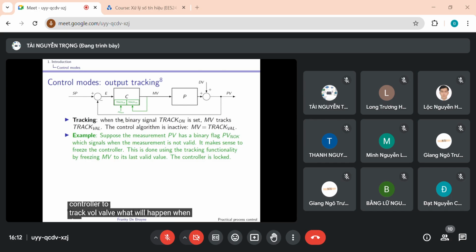What will happen when the sensor flags a signal measurement that is wrong? Well, this one will go to 1, and MV will track itself, so that you have here at the output the last value that you have in automatic mode. Okay, so the controller is frozen with the last active value of MV. The controller is locked, and of course in the human-machine interface there should be a warning for the operator to tell him that there is something wrong with the measurement, but at least nothing goes wrong in the sense that the controller is now locked.